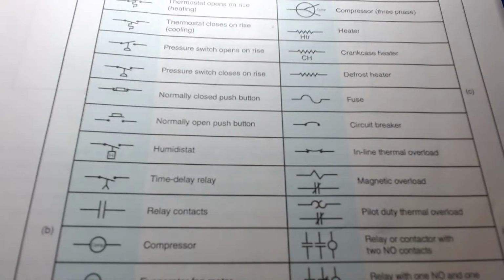So if you grab two pressure switches out of the box and you're not sure which one it is, your high pressure switch will always be closed out of the box because there's no pressure to open it. Your low pressure switch will be open because there's nothing to close it. Okay. Push buttons. You'll see these on your rollout limits or some high limits depending on the style you have. So normally closed push button, normally open push button. Normally closed is normally your rollout limits on those there.